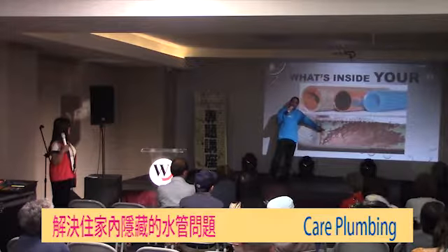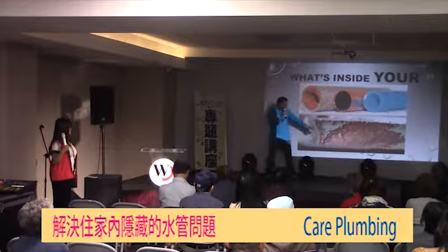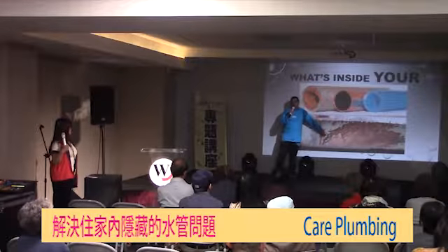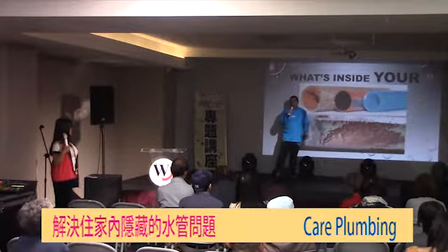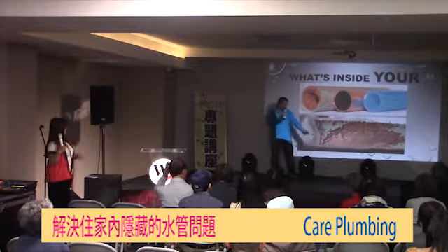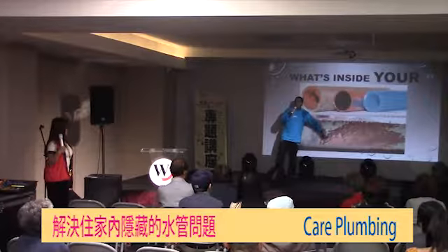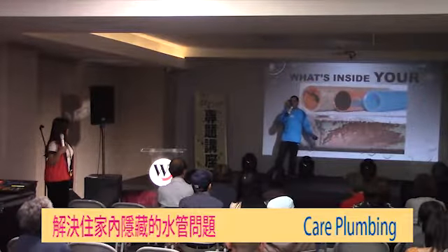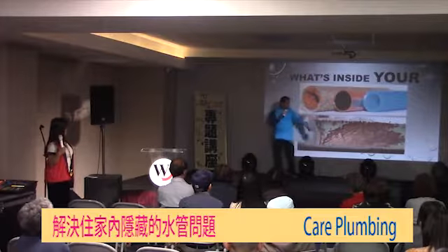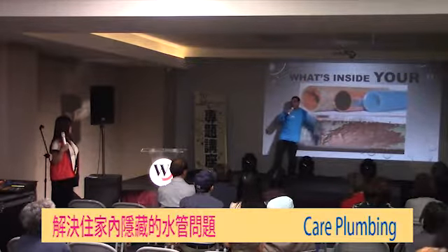If it's not a good quality copper, it's M-type. This is what happens inside. The chlorines and chloramines will deteriorate it. The friction from the water will start to peel off layers, and eventually you're going to have a leak coming from that pipe. Remember this picture, it's very important for what I have to say next.